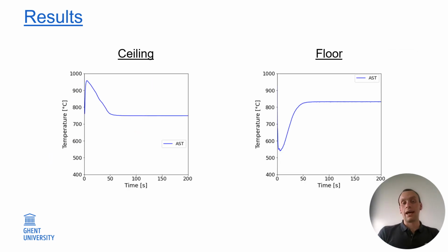With respect to the adiabatic surface temperature, I would like to highlight that there is an important difference between how we would measure it in an experiment with, for example, a plate thermometer, and how we apply it in calculations. If we're looking at experiments, we have changing conditions. Our temperatures change, flows change, and the resulting convection coefficient will also change. If we look at the way we use it in calculation, we just use a fixed value. And FDS actually allows you to compare the two.